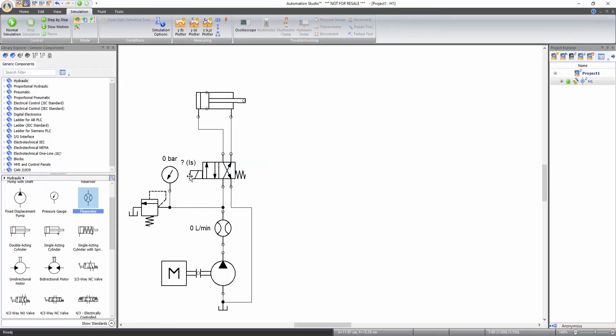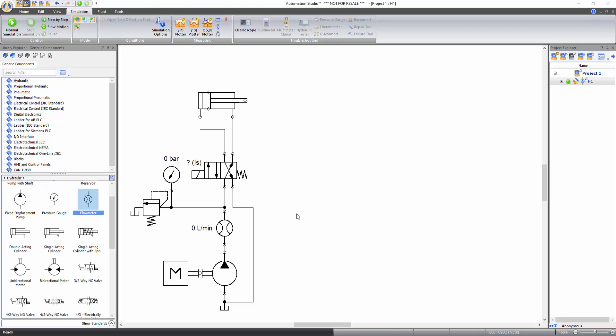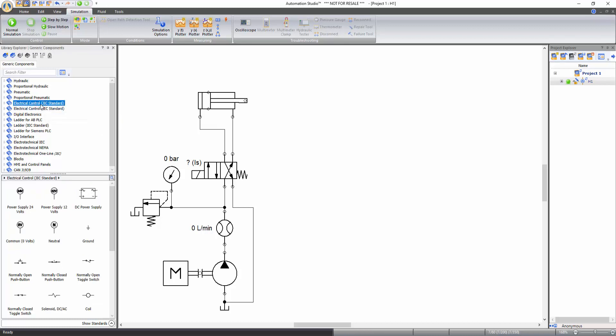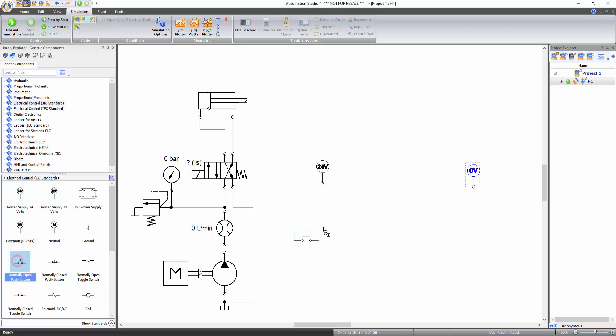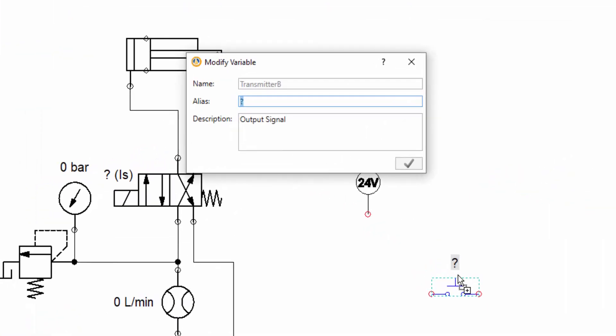Now the valve is transformed into an electrically controlled solenoid valve, and the question mark symbol above the solenoid signifies that it needs an electrical input signal to change spool position. In order to provide the electrical signal for valve operation, you need to create a simple electrical control circuit. All the components needed to create this circuit are available in the electrical control main library. Select the electrical control IEC standard library and drag and drop a power supply 24V, a common 0V, and a normally open push button.